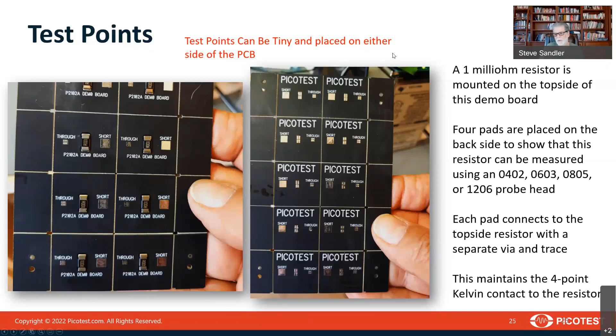When we actually make measurements with probes, we can do that using one of two choices. One choice is to use two one-port probes, each one providing two of the contacts. Another option is to use a four-point Kelvin probe like our P2102 that does two-port impedance all in one head. There are pros and cons to both sides, and there's nothing that's perfect.